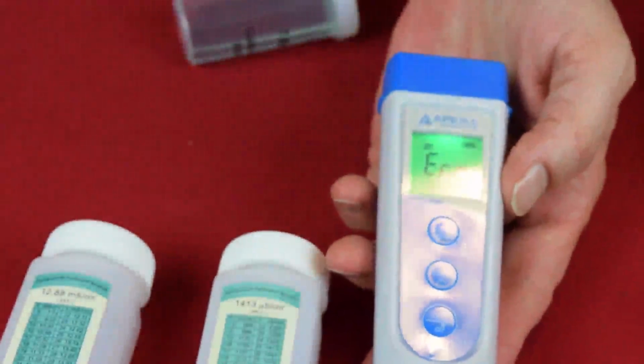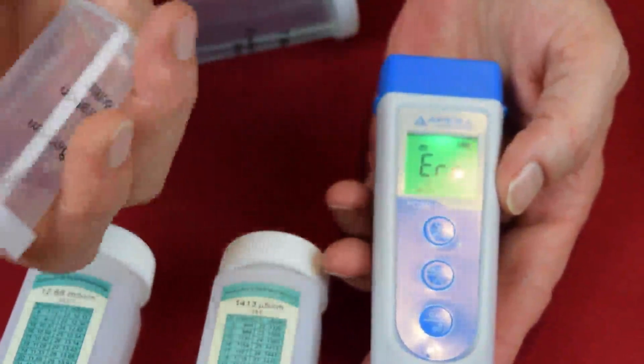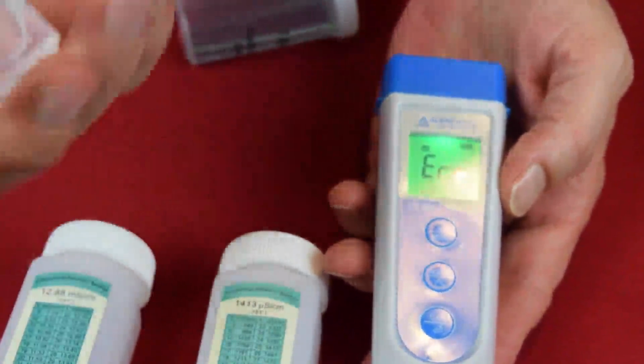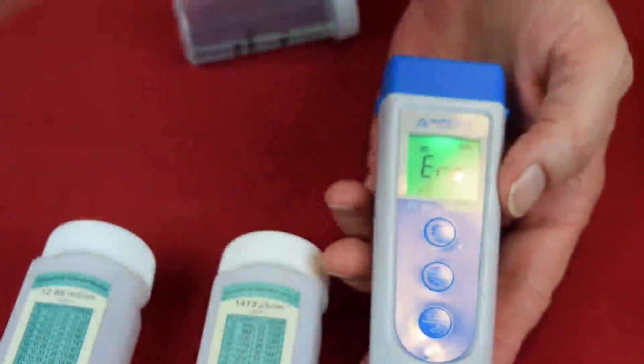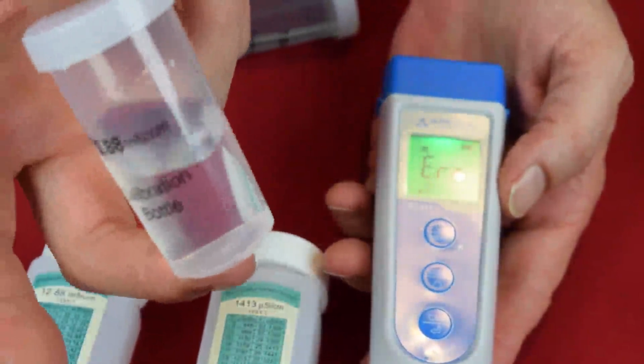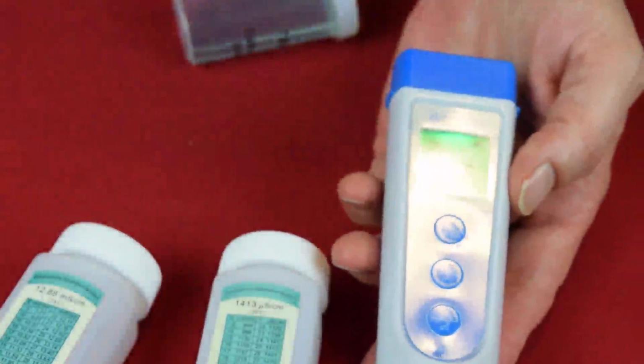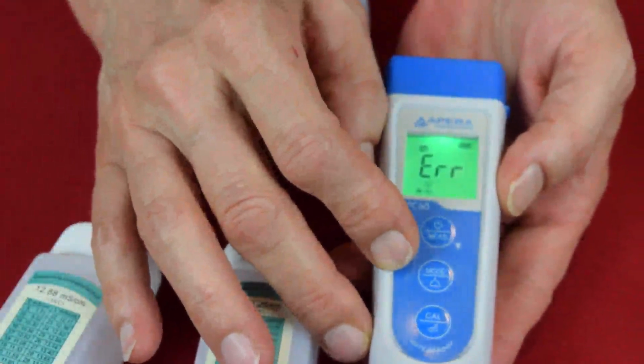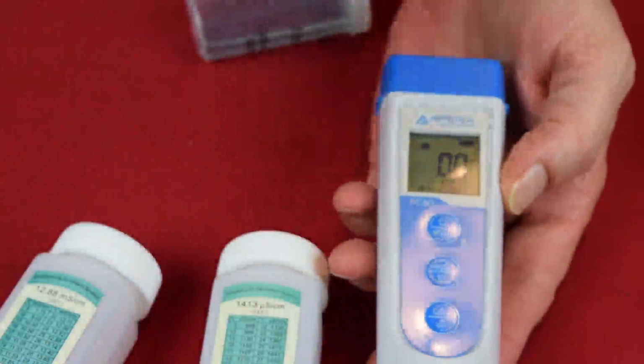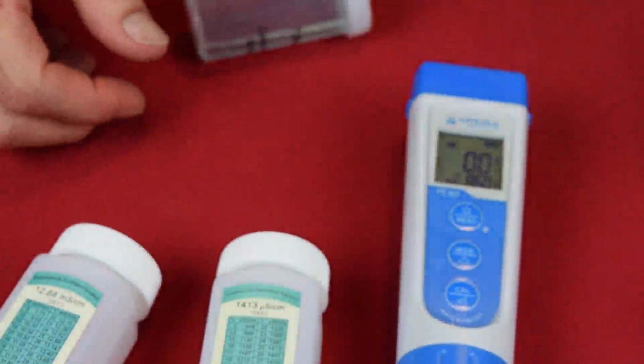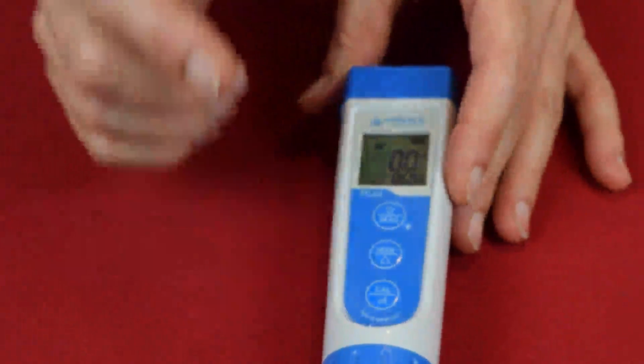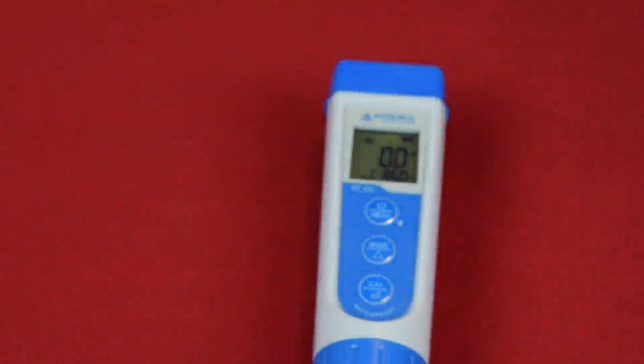And then of course those have their own bottles, and these are nice too because when you put the cap on, these don't leak, and you can leave it in there. And they say you can use this calibration for the conductivity about 5 times, and then you have to get some more. So I'm going to go out of cal mode by hitting measure, and let me get some stuff together here. And by the way, every time you're going from solution to solution, you want to rinse it in distilled water, and then dry this bulb so you don't take any of that water into whatever solution you're using.